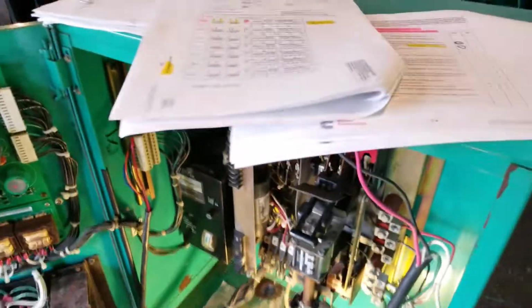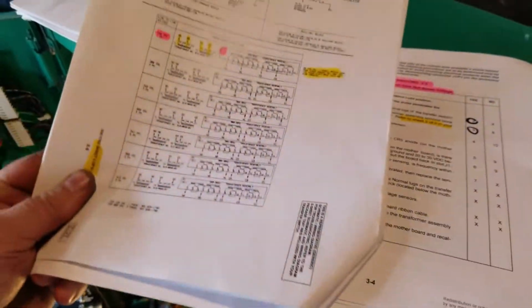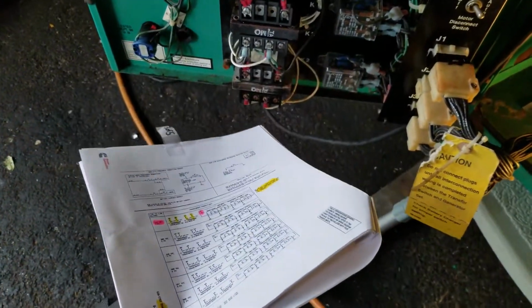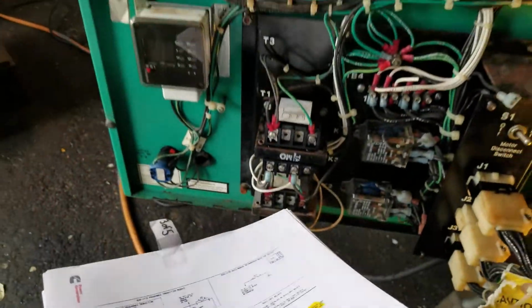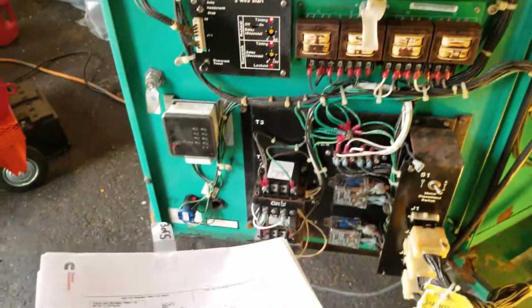I started troubleshooting all this using the manuals, as you can see, and basically it's quite simple. The first step is to check these transformers down here to see if they have the proper voltages, which they do, one for line side, the other for generator.